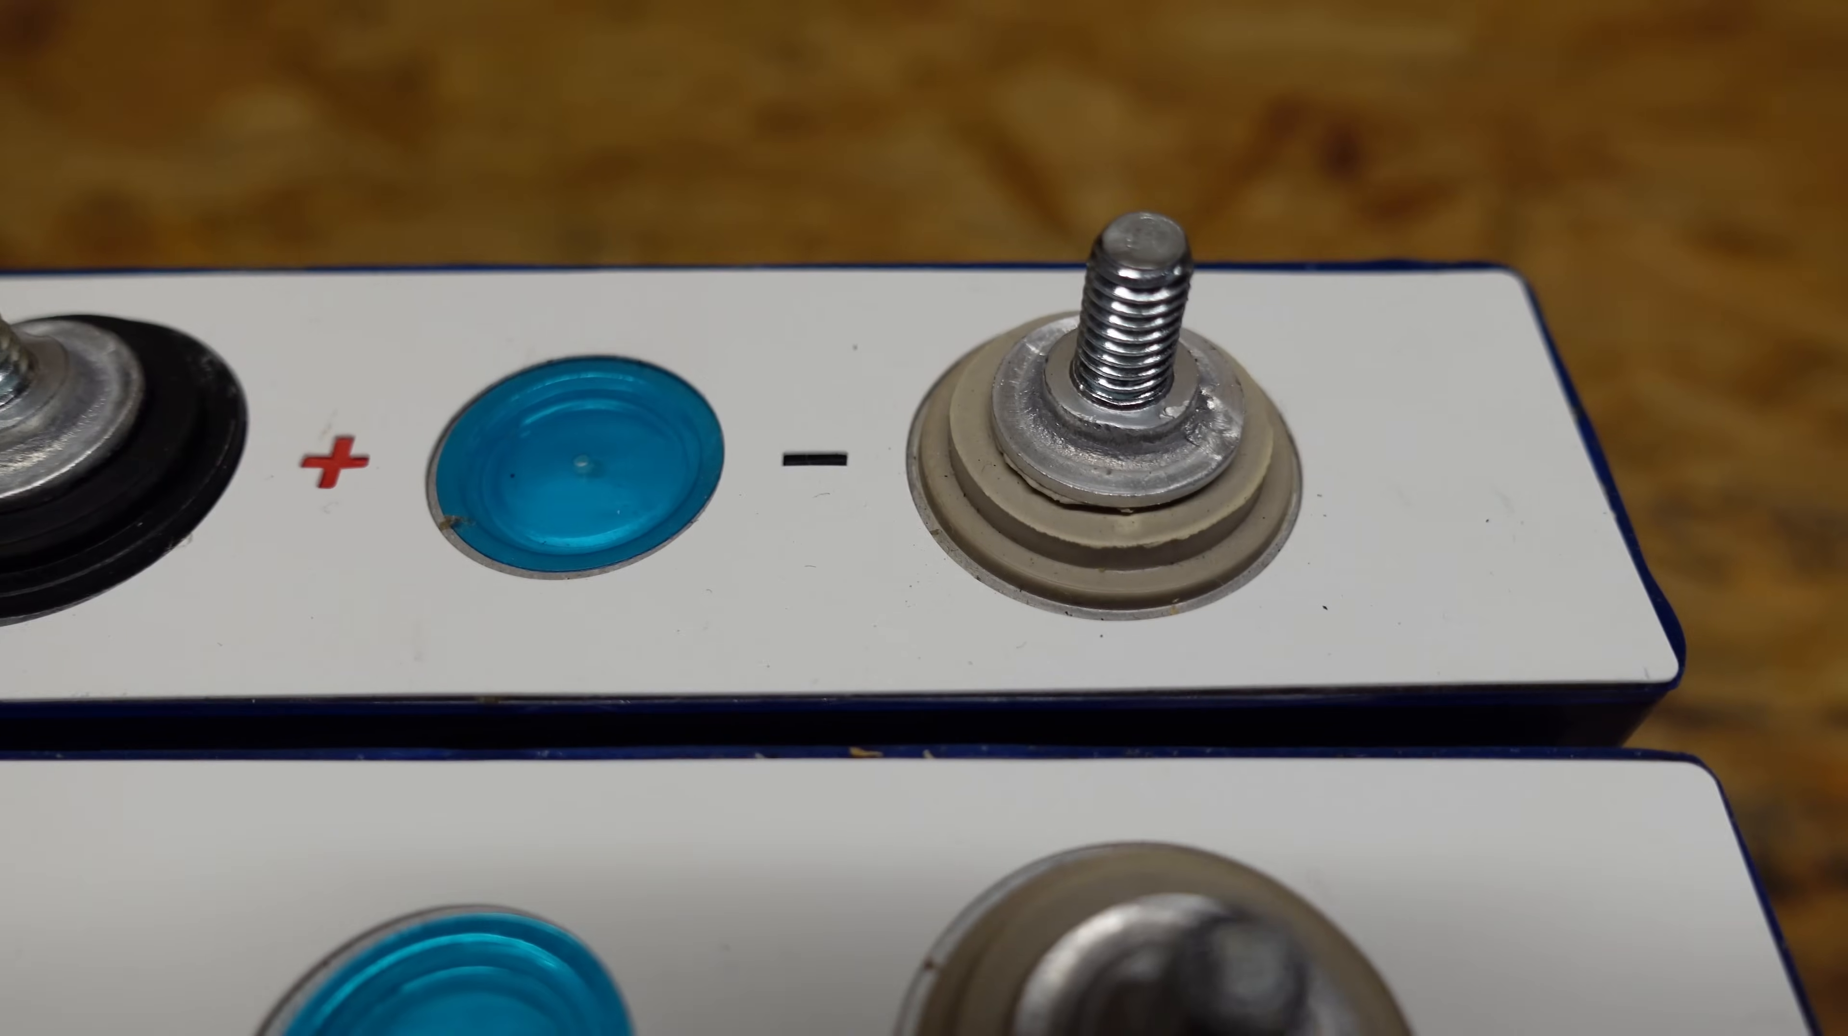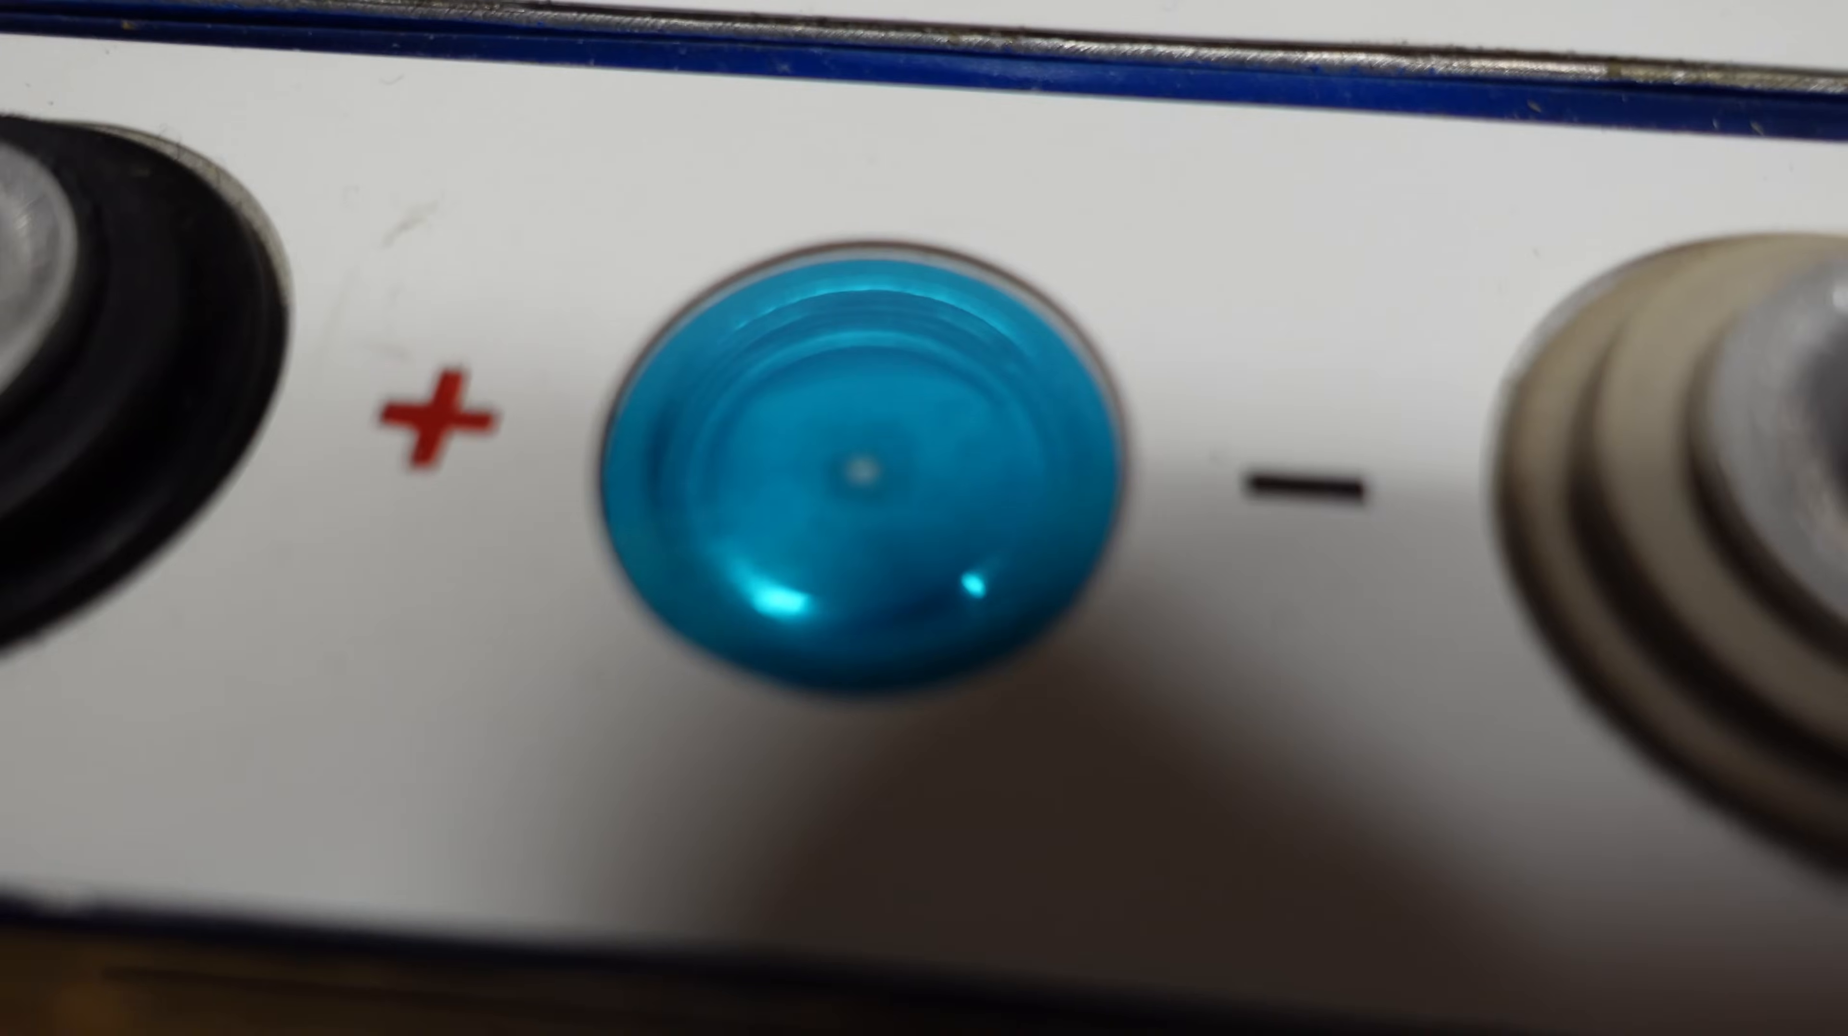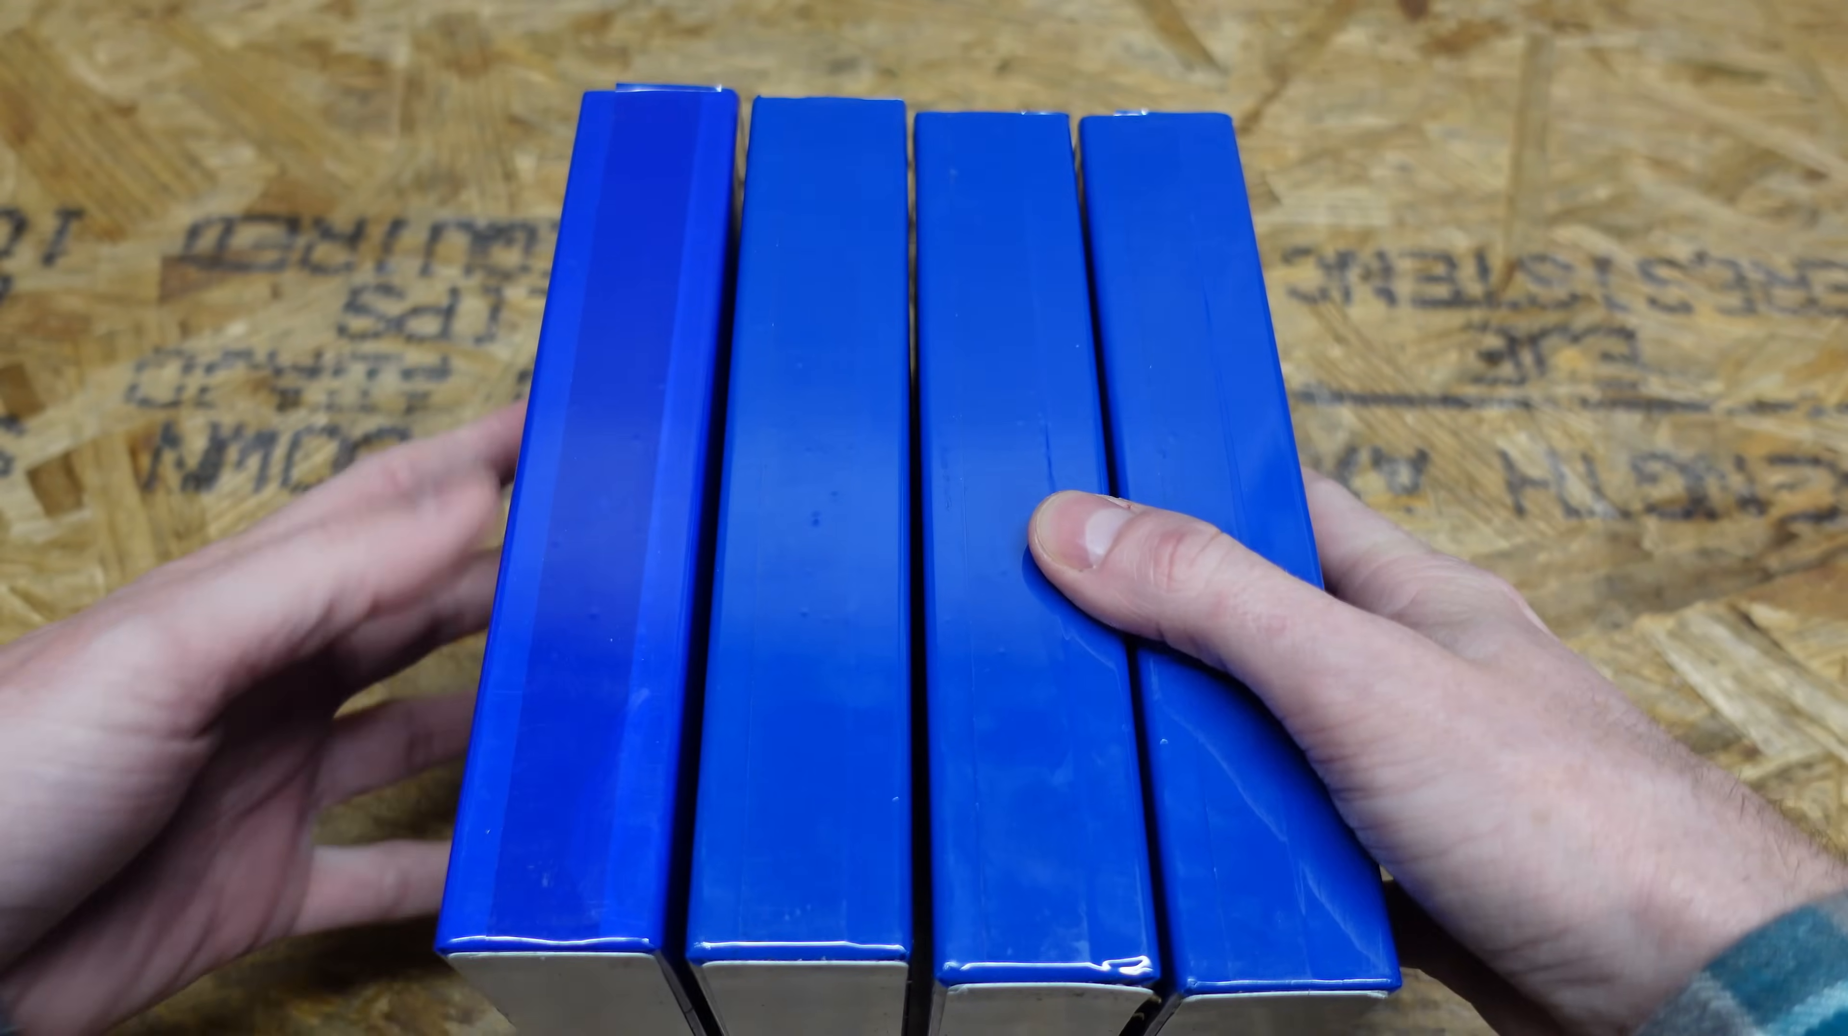So these cells do have welded posts which actually look very nice. They did a good job welding these posts on. Looking over the vents three of the four look good. This last one down here has got a little bit of corrosion or I really don't know what's going on down there. It looks like maybe moisture or something got in. Looking at the side profile again you can see how bloated these cells are. They are not flat.